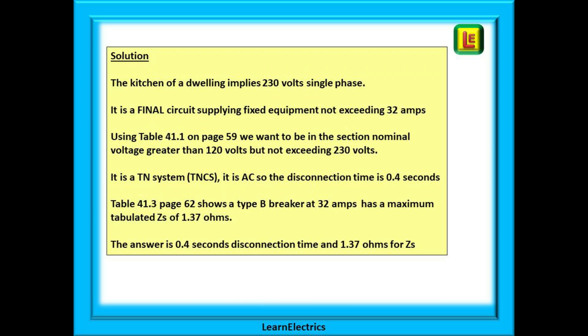We are expected to make some assumptions: a kitchen in a dwelling implies 230 volts nominal and single phase; we can also assume it is a final circuit supplying fixed equipment not exceeding 32 amps. Looking at table 41.1 on page 59, we choose the second block — the nominal voltage is greater than 120 volts but does not exceed 230 volts. It is a TN system, it is AC, and where the column and row cross is our answer: 0.4 seconds. The next part of the answer is found on page 62 in table 41.3, because it is a BS EN 60898 circuit breaker, type B, 32 amps — and below 32 is the answer: 1.37 ohms. So our complete answer is 0.4 second disconnection time and 1.37 ohms for ZS.